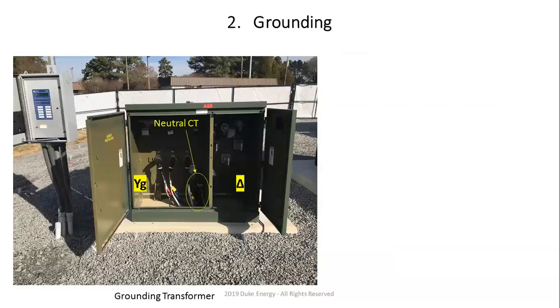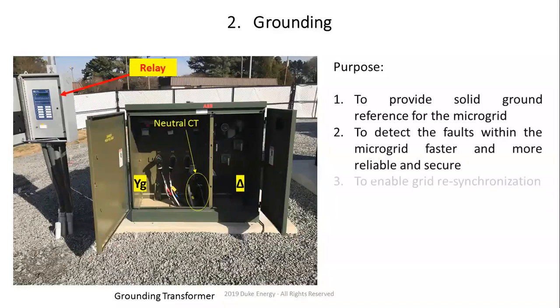And what you do is you put this neutral CT right there between the neutral and the ground, because that becomes the main source for pickup of line to ground faults within the microgrid, right? And then you have a relay over there. So you tie the neutral CT over to the relay, and then you have to do analysis to see what kind of settings we need. So the main purpose for the grounding transformer is actually threefold, right? You have to have a solid ground reference on the 12.47 kV side, because the PV system and battery are ungrounded, right?